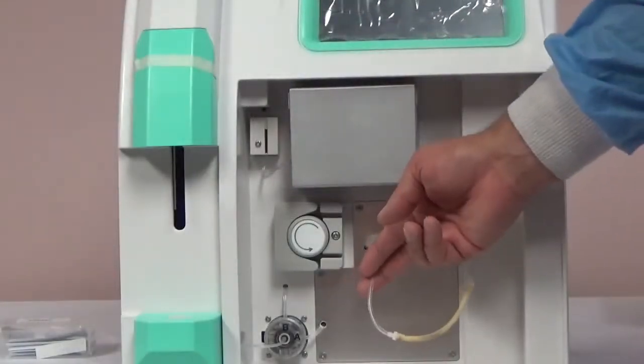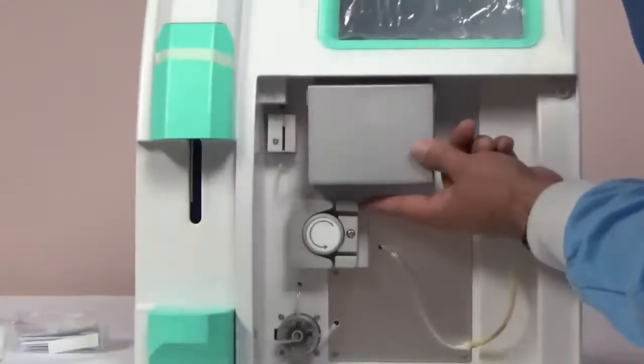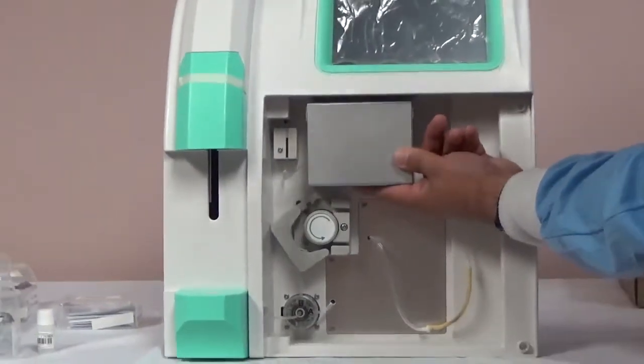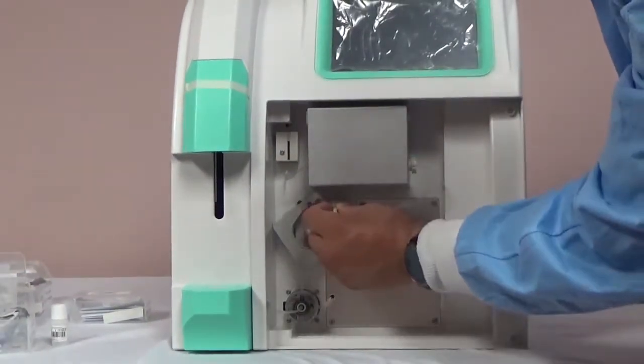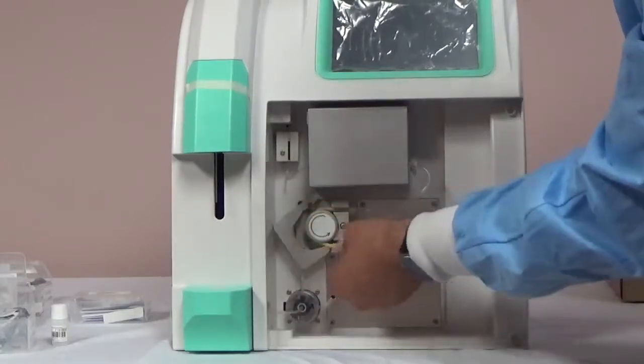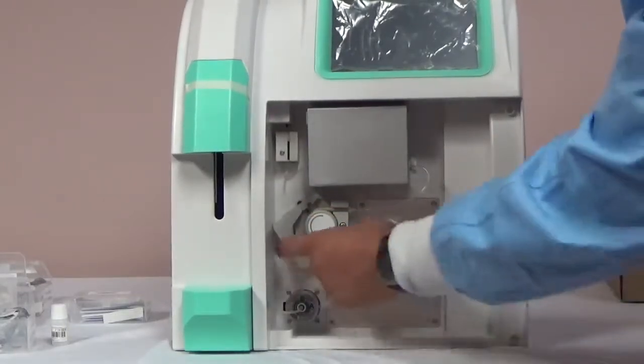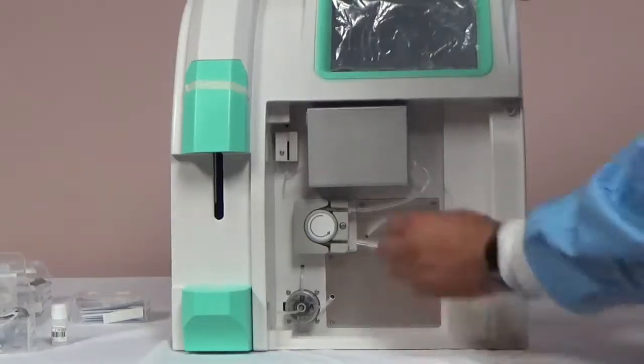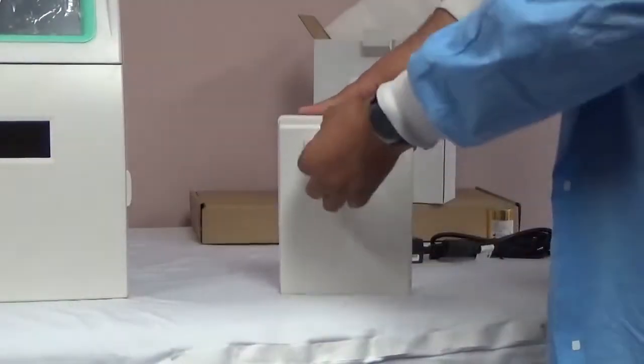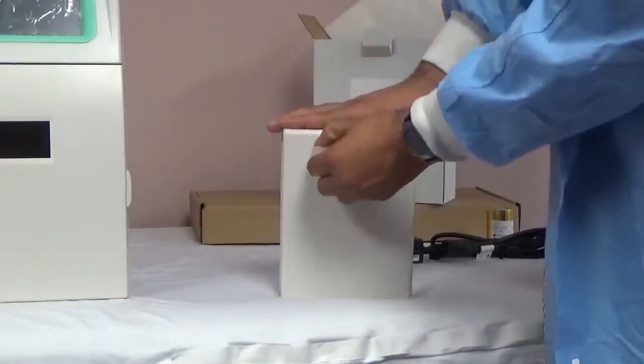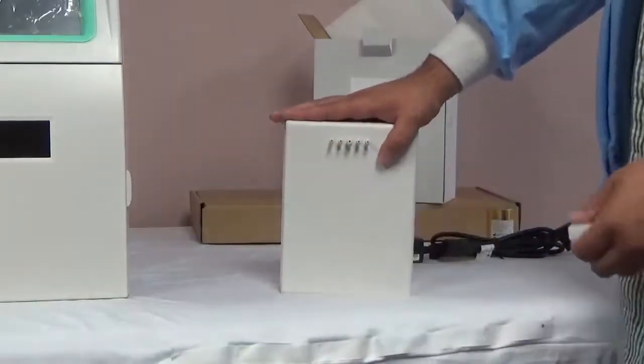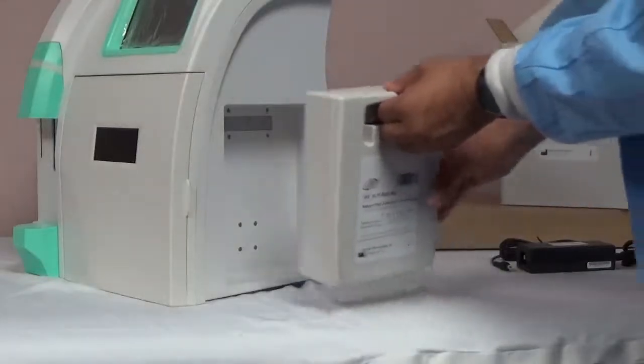Secure the pump tubing and peristaltic pump by unclipping the pump lock and stretching the tubing around the pump, and then relock the clip. The reagent pack can be installed in the slot on the side of the analyzer. Remove the pack from the box and remove the rubber piece on the back. Slide it into place, pushing gently to secure it.